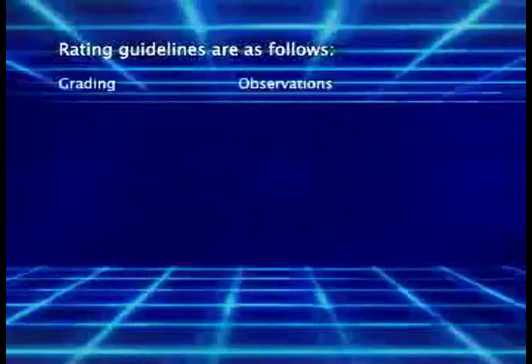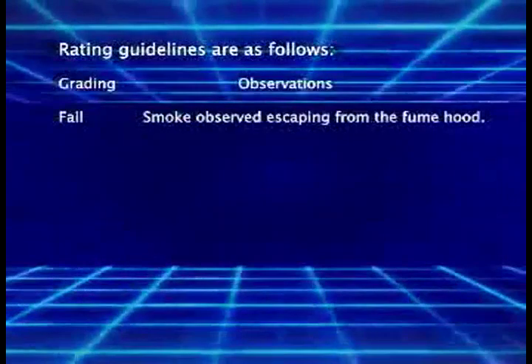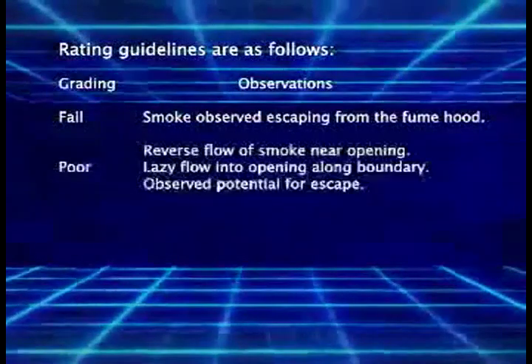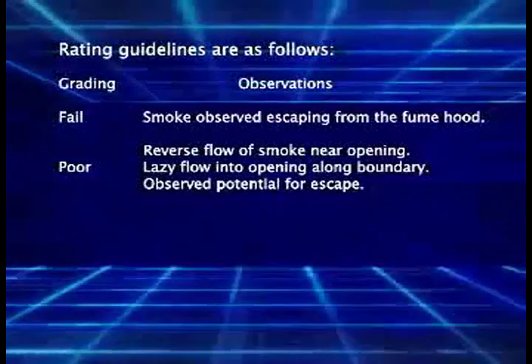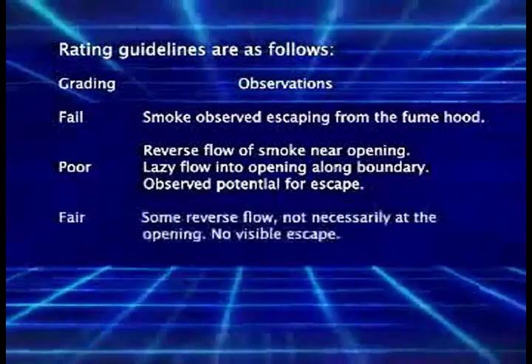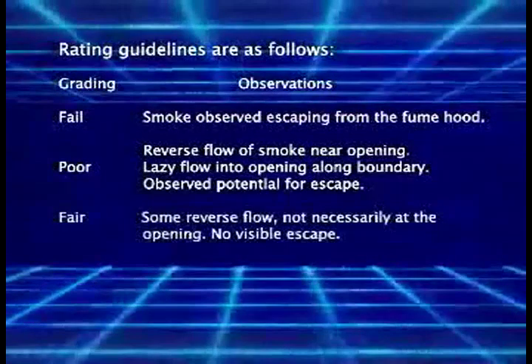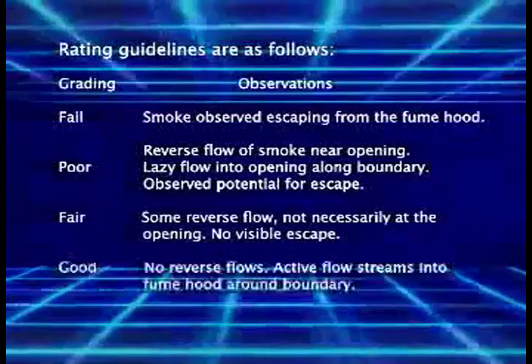As with the local smoke visualization test, the fume hood is given one of four ratings depending on the outcome of the observations taken during the test.